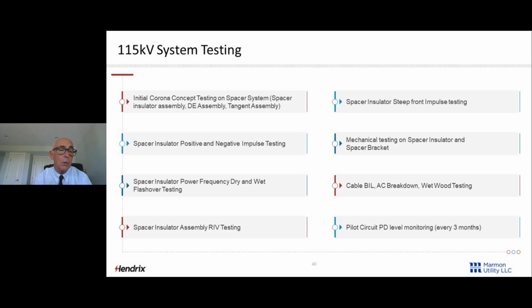We did initial Corona concept testing on the spacer system, the assembly, the dead end, and the tangent. We did positive and negative impulse testing. We did power frequency dry and wet flashover testing. We did RIV testing. And again, these are all according to our standards, since we don't have standards from ICEA or IEEE or ASTM yet.